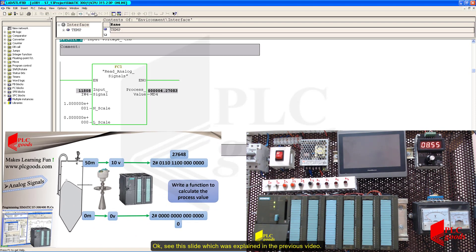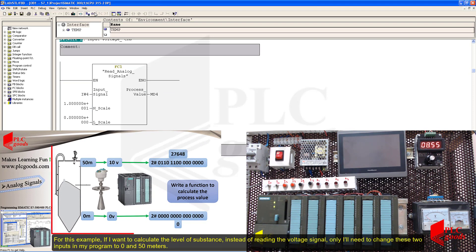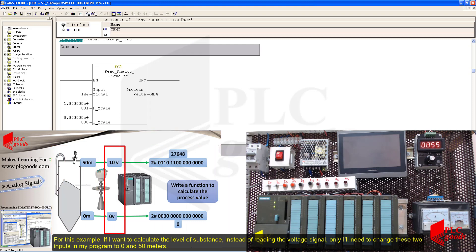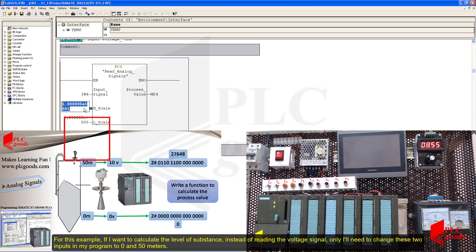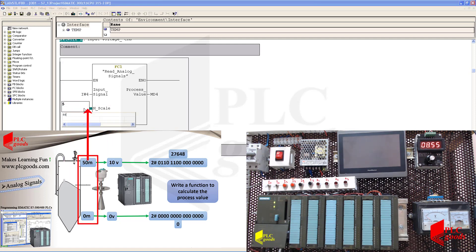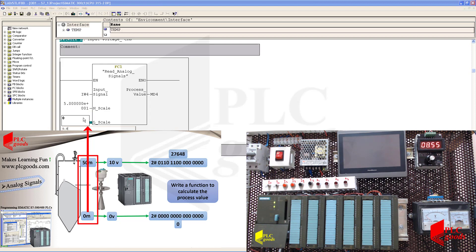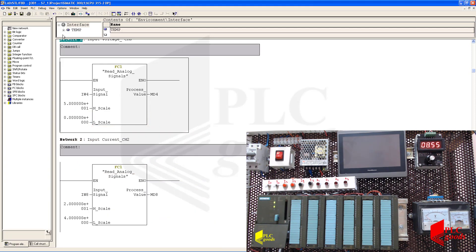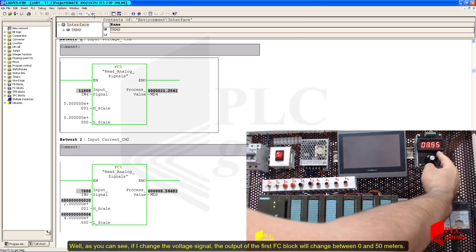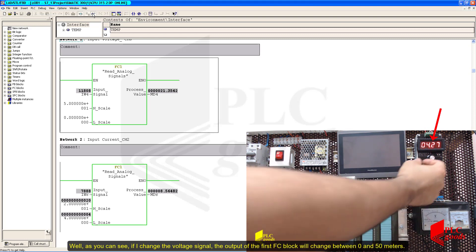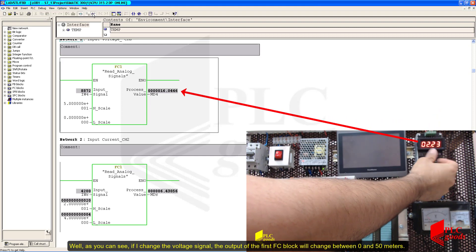See this slide, which was explained in the previous video. For this example, if I want to calculate the level of a substance instead of reading the voltage signal, I only need to change these two inputs in my program to 0 and 50 meters. As you can see, if I change the voltage signal, the output of the first FC block will change between 0 and 50 meters.